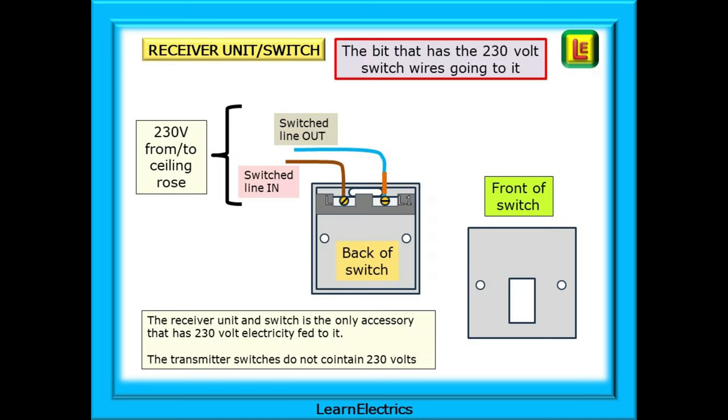Looking now at kinetic switches, how are they going to work? We should start with the receiver unit which may or may not include a switch as well. As these are light switches in this example, it will make sense to talk about a combined receiver and switch accessory. This is the bit that has the 230 volt switch wires going to it. We don't need a neutral, just connect the incoming and outgoing switch wires into the back of the switch.